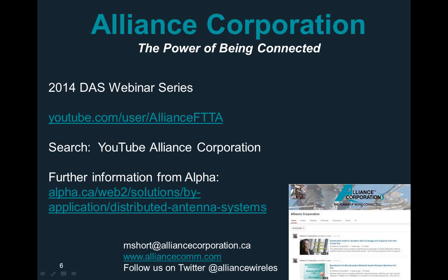One more question, and I haven't had any submitted, so if there aren't any submitted, this will be our last question. Referring to your presentation, how prevalent is this power scheme? Is it in use? Is it mainstream? Oh, yes, it is. In fact, it's been adopted by some of the larger service providers as their preferred method of powering indoor DAS. It's been enabled over the last few months with the advent of the Aggregator, where we now have addressed essentially all of the issues with indoor power. In the past, we could do anything under 100 watts, but now with the Aggregator, we can address the larger nodes as well.